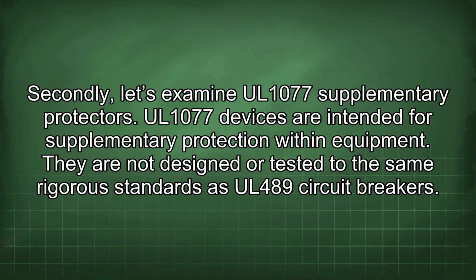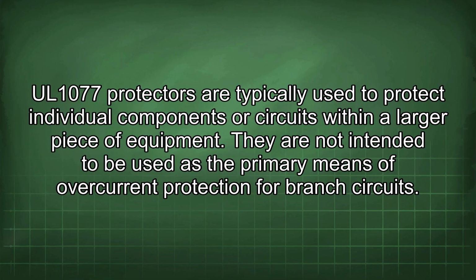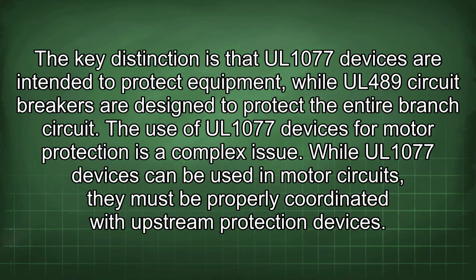Secondly, let's examine UL 1077 supplementary protectors. UL 1077 devices are intended for supplementary protection within equipment. They are not designed or tested to the same rigorous standards as UL 489 circuit breakers. UL 1077 protectors are typically used to protect individual components or circuits within a larger piece of equipment. They are not intended to be used as the primary means of overcurrent protection for branch circuits. The key distinction is that UL 1077 devices are intended to protect equipment, while UL 489 circuit breakers are designed to protect the entire branch circuit.